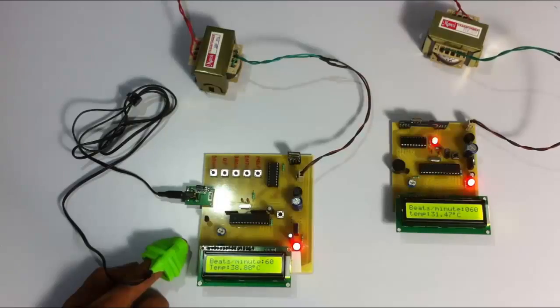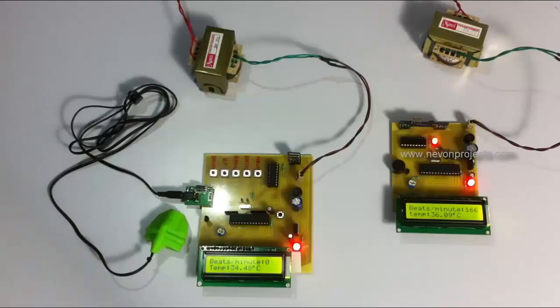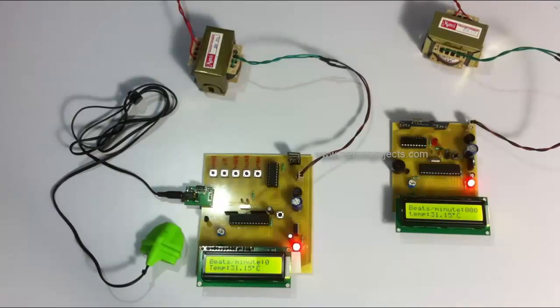Now let's check the heartbeat detection. Let's simulate a lower heartbeat by removing the module. That simulates the heartbeat going below permissible limits. As you can see, as soon as the heartbeat went below a particular limit, the system sounded a buzzer to alert the doctor that the patient's heartbeat has gone below permissible limits, so that the doctor can react immediately and save the patient in time.